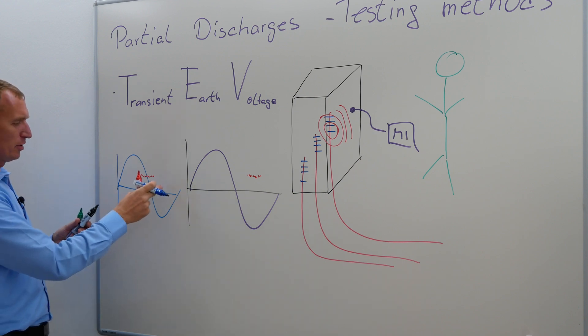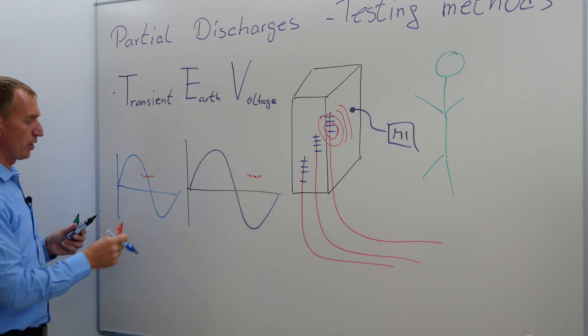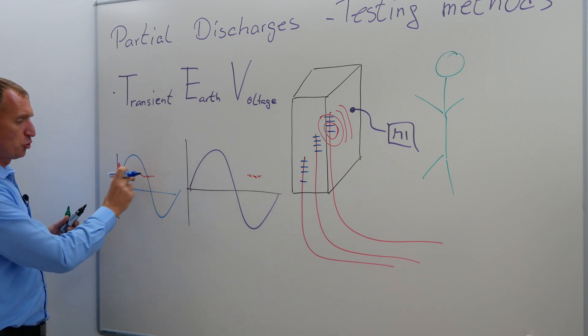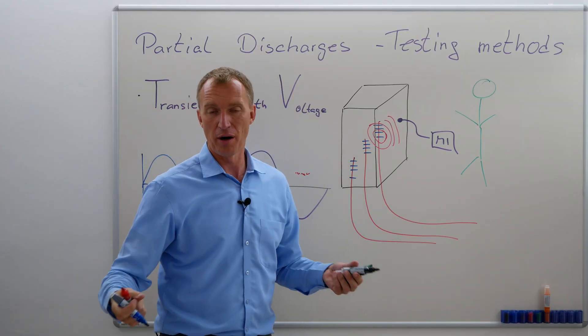I don't really know if it's on ground or in high voltage. Could be either of them, right? And I do not know the phase shift I have right now, but I'm quite sure I do have a partial discharge in there.